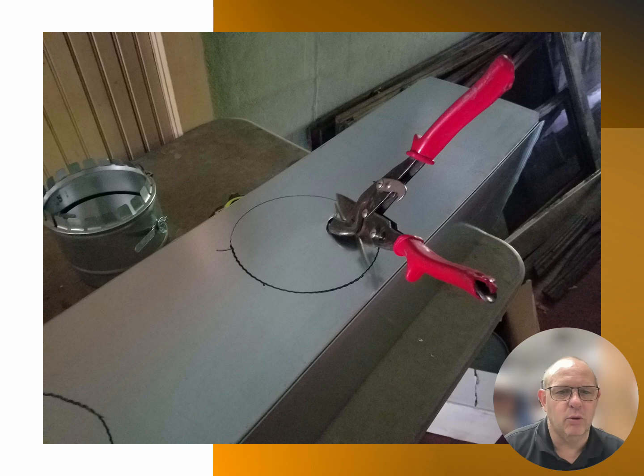Okay, we got that hole in our ductwork, and now we're going to insert our aviation snips into the ductwork. And hopefully you have time to work with these aviation snips, but we're just going to work our way around that circle. We want to try to cut right on the line, because that's where those tabs are going to bend over and catch that ductwork and hold that takeoff in place, so that we are capable of moving air into the branch ductwork itself. So we'll take that aviation snip and we'll go around the ductwork hole there, and then we'll insert that takeoff into it, as we're going to see within our next picture.